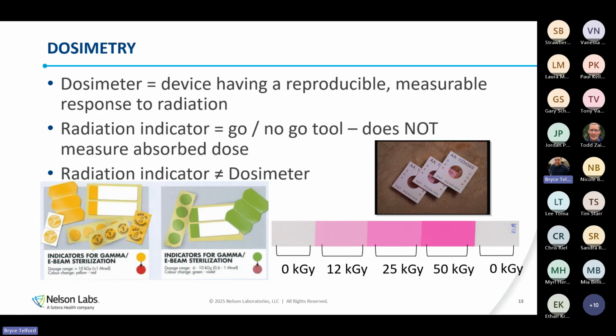So I like to convey things with stories. Quick story: there is a requirement in the standards that irradiated and non-irradiated products be segregated. And it specifically calls out that radiation indicators are not acceptable. So you really need some physical tracking, such as having cages, fencing, as well as tracking such as batches, batch numbers, things like that. You really can't rely on radiation indicators.